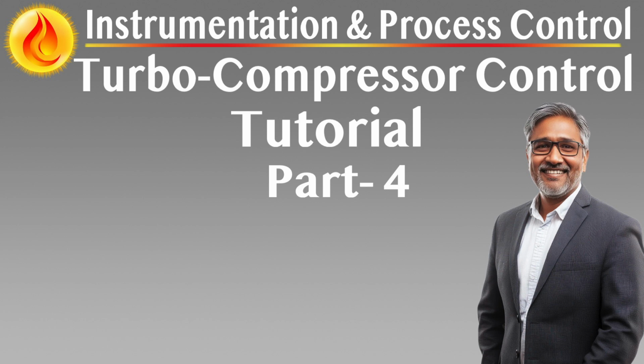Startup and reboot sequence. The vendor must define where each logic block resides, volatile versus non-volatile memory, how the system restores from power loss, and the time to full functional recovery after reboot, to be verified during FAT.